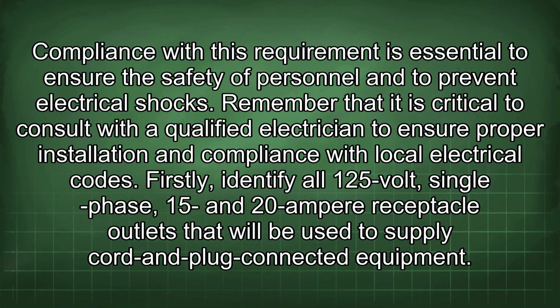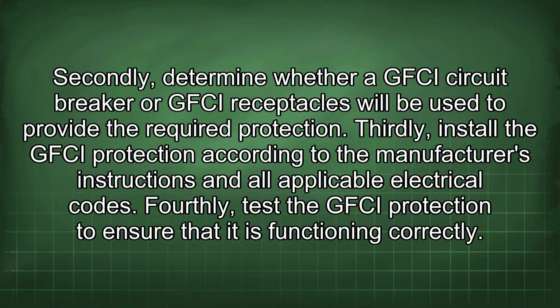Firstly, identify all 125-volt single-phase, 15 and 20 ampere receptacle outlets that will be used to supply cord and plug-connected equipment. Secondly, determine whether a GFCI circuit breaker or GFCI receptacles will be used to provide the required protection. Thirdly, install the GFCI protection according to the manufacturer's instructions and all applicable electrical codes. Fourthly, test the GFCI protection to ensure that it is functioning correctly.